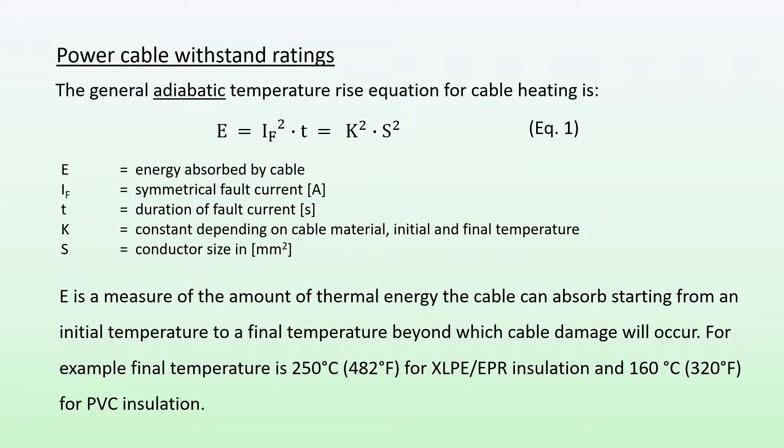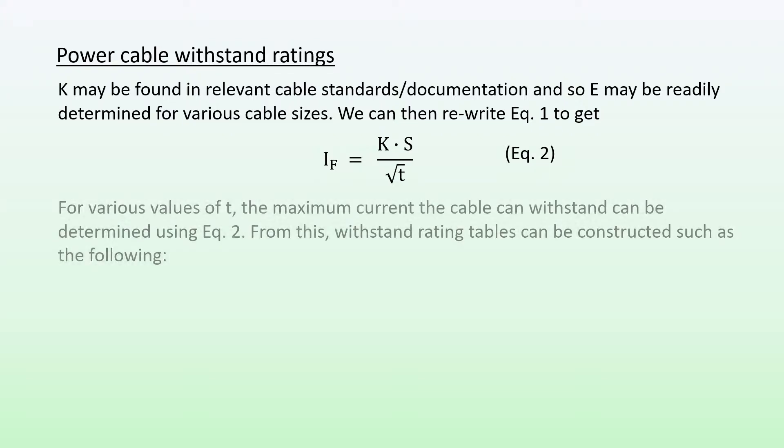For example, final temperature is 250 degrees for XLPE and 160 degrees for PVC. K may be found in relevant cable standards documentation, and so E may be determined for various cable sizes. We can then rewrite equation one to get that the fault current is the product of K and the cable size S divided by the square root of t. For various values of t, the maximum current the cable can withstand can be determined using equation two.